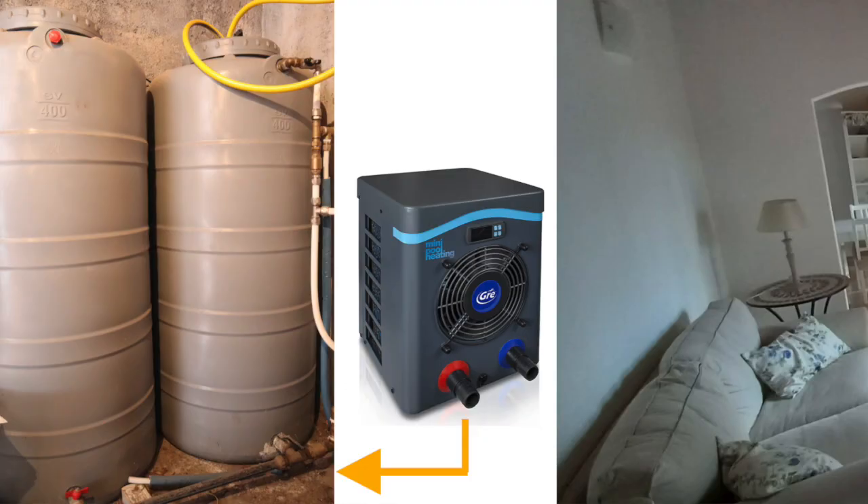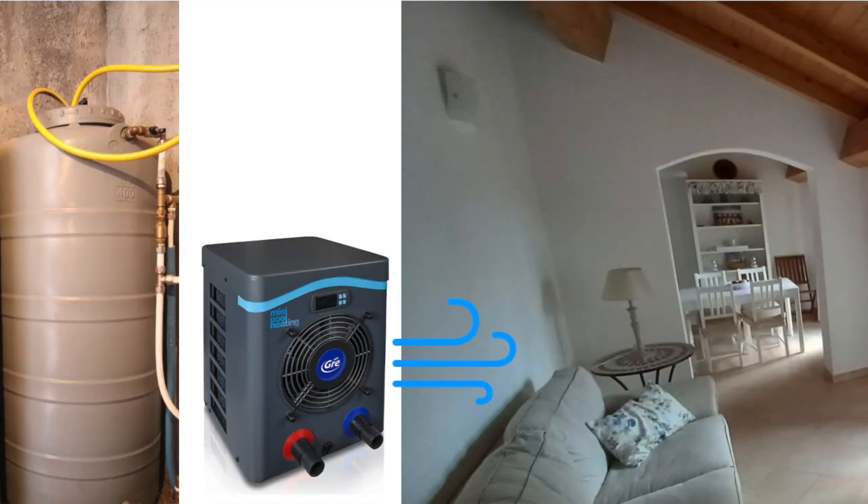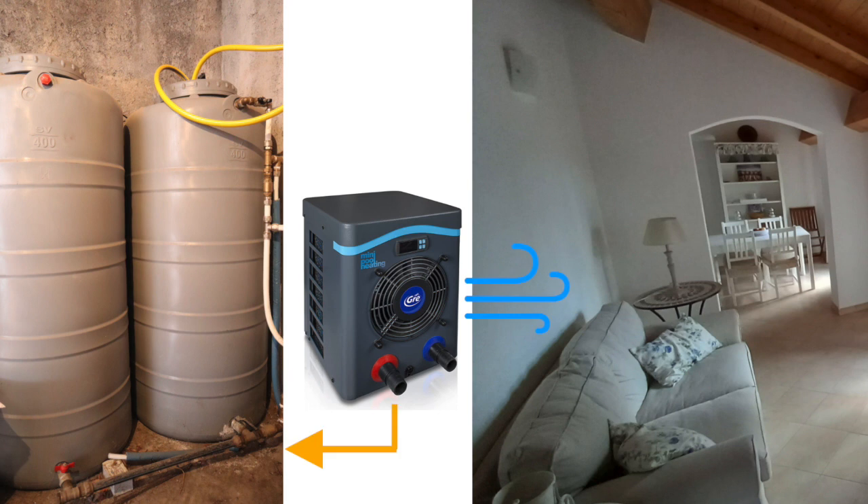This heat pump has been designed to heat up a swimming pool, so it has a warm water circuit on one side. On the cold side, it draws heat from cold air and transfers it into the water. If you can supply cold water to the warm side, the temperature difference between that cold water and the air is much smaller than between, say, warm air in a living room and cold air outside. That means the heat pump will have an easier job and will reward you with more efficiency.